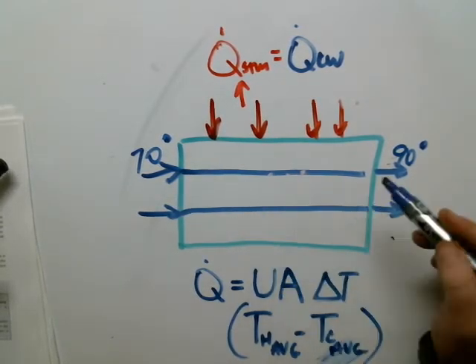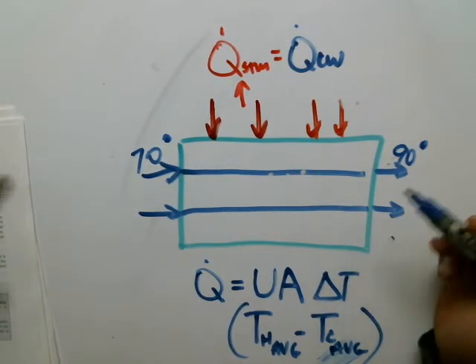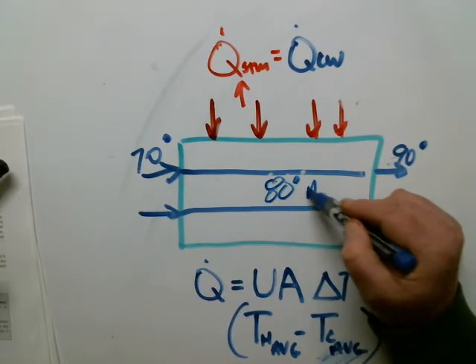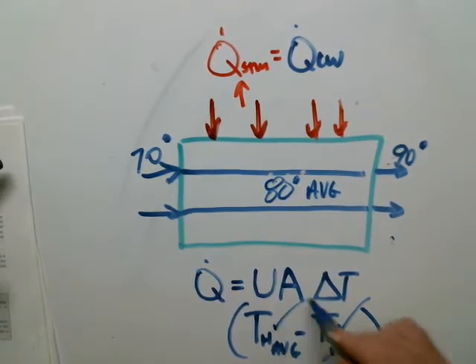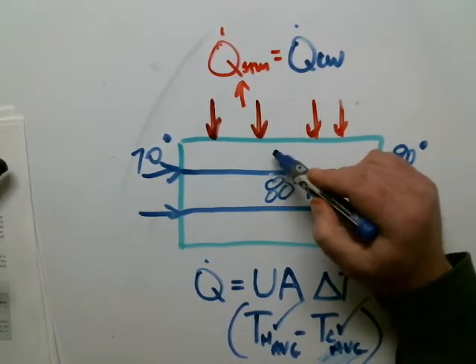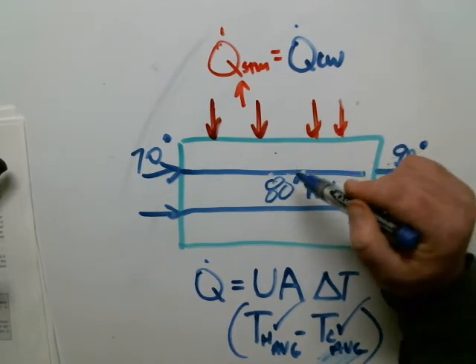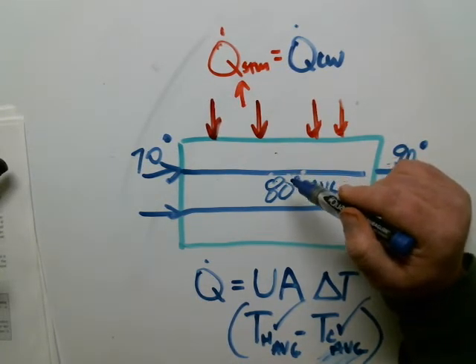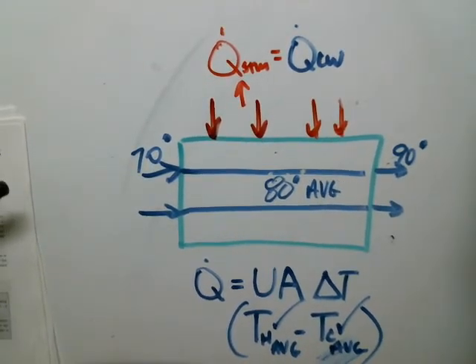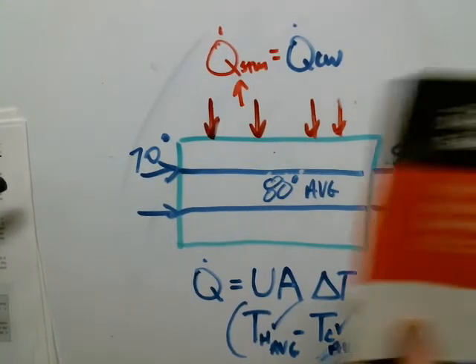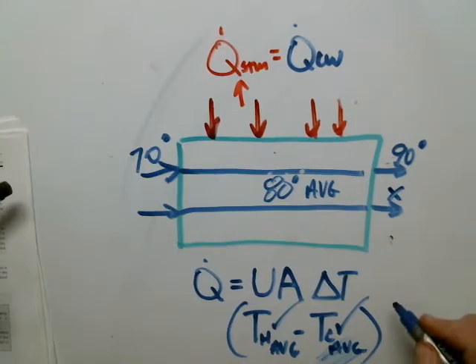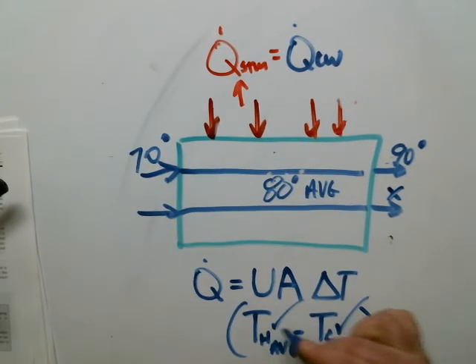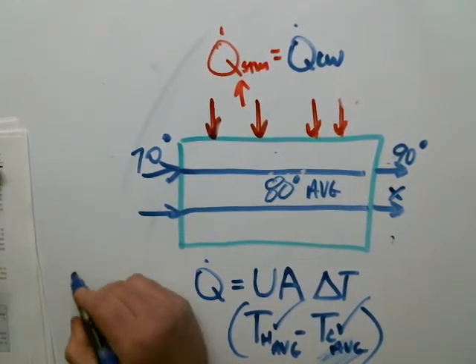That's what that Delta T is. So if I said I had 70 degree inlet water on my circ water and 90 degree outlet temperature of the circ water, the average temperature is 70 plus 90 divided by 2, or 80 degree average temperature. That's the average temperature of my cold. The average temperature of the hot—well, whatever the shell pressure is here, you use the corresponding saturation temperature. So you just look that up. If you are operating at 1.2 psia in your condenser, look up that saturation temperature in your steam tables.